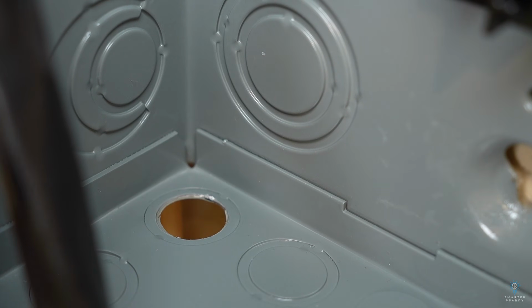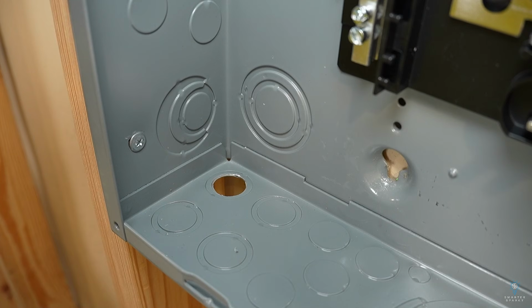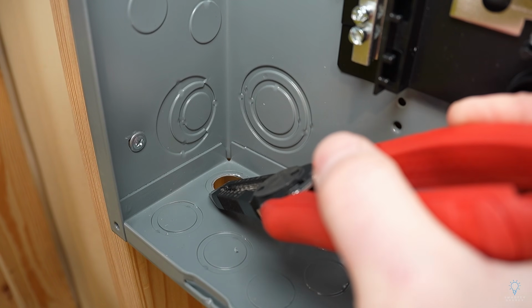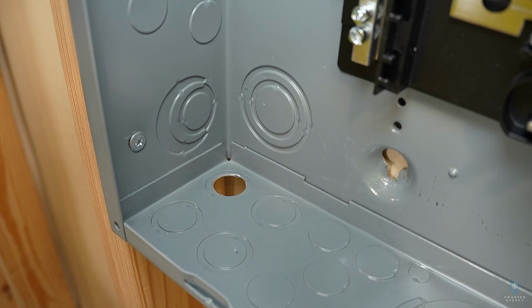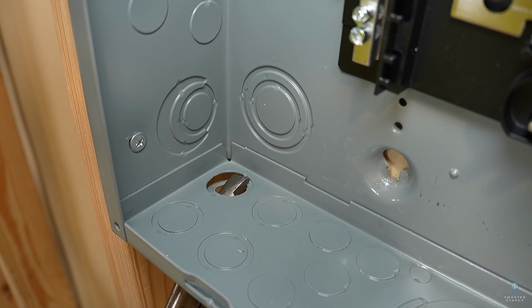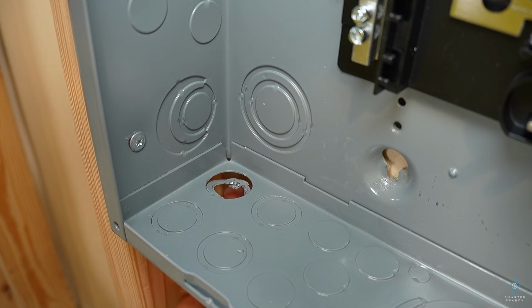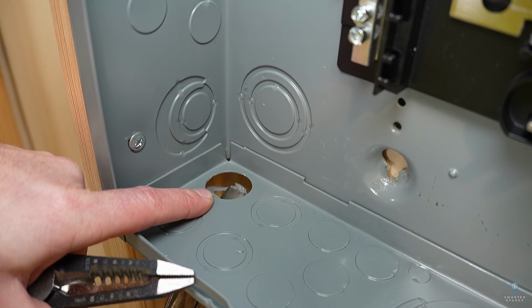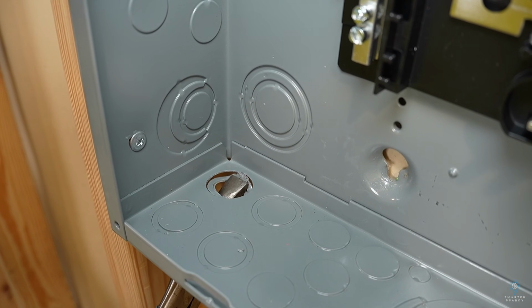But that actually only knocked out the 1/2 inch portion of that. Now we've got this concentric piece that we need to knock out as well. In this case, there's a few tools that we could do with this. The problem is it's actually connected at this point and this point. So it's actually connected at 2 different points. So I like a lineman's in this case. I can come in the bottom here and grab that single side and wiggle it back and forth, and it will eventually shear off. There it goes. And then it's just a matter of grabbing it and pulling it back. You could probably just do this by hand. I'm just gonna grab this with the lineman's and pull it backwards and wiggle this connection point right here a few times, and it will eventually shear off as well.